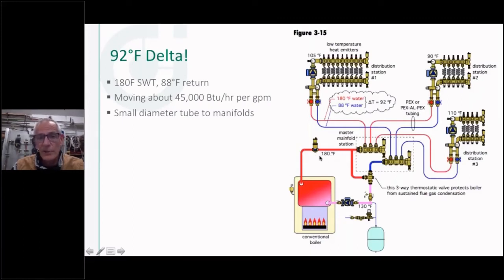To be able to run at that 180 degrees, I probably wouldn't put a mod con boiler into that condition, other than if I wanted the modulation aspect of it, I'd still have that, even though I'm running way out of where it's ever going to condense. And that's why in this example we've got a return protection valve on this, to make sure I'm always maintaining a 130 degree return to that cast iron boiler, so I don't start sweating or condensing in that boiler. So just a basic three-way thermostatic valve will protect that boiler from running too cold.